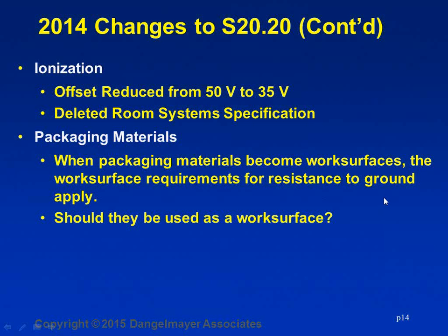And that would be a classic situation where this would violate 2020, because if you were to measure resistance from the top of that ESD bag to ground, in most cases it's not going to be less than 1 × 10⁹ ohms.